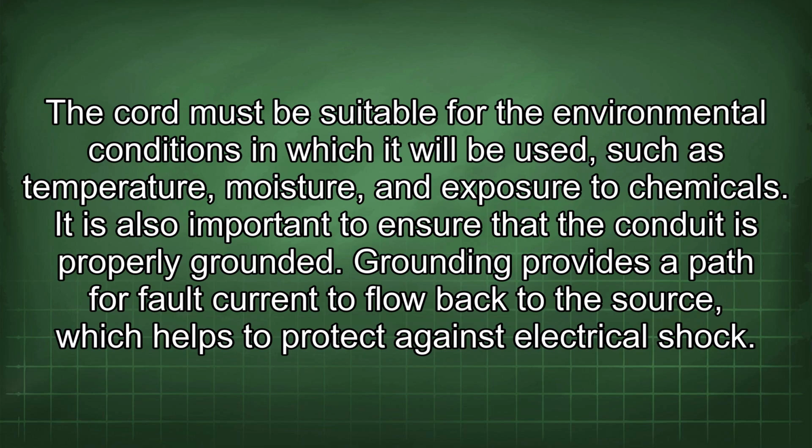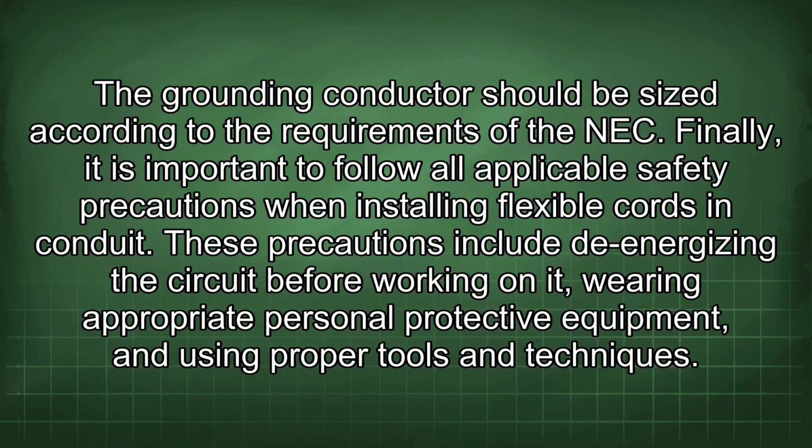exposure to chemicals. It is also important to ensure that the conduit is properly grounded. Grounding provides a path for fault current to flow back to the source, which helps to protect against electrical shock. The grounding conductor should be sized according to the requirements of the NEC.